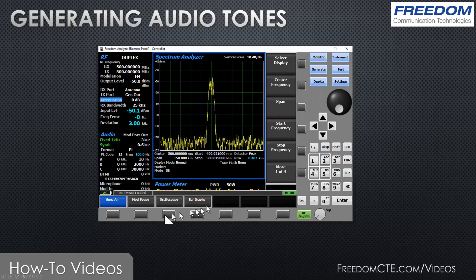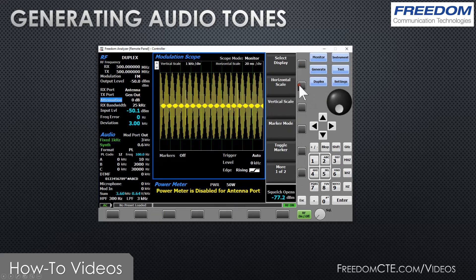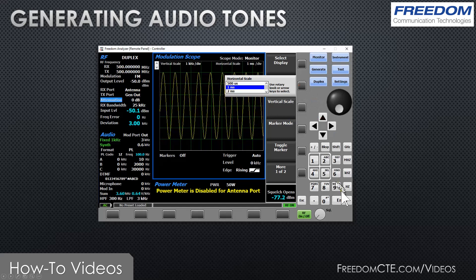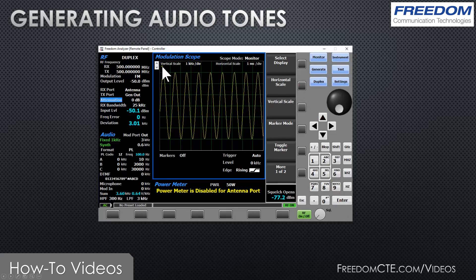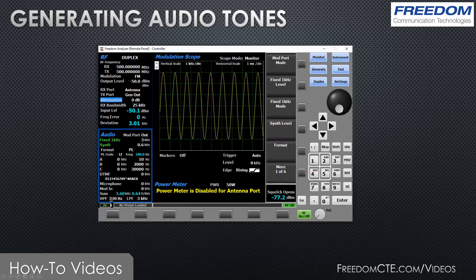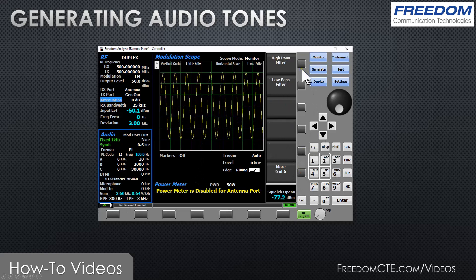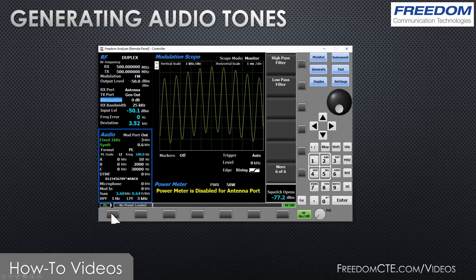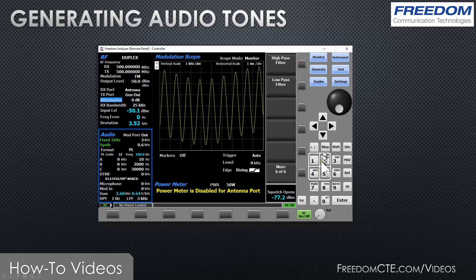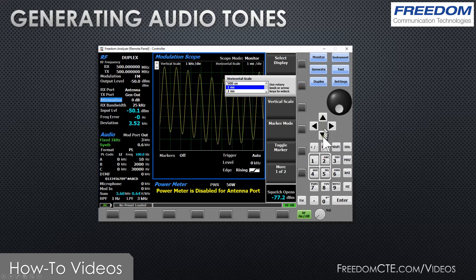I'm going to show you the mod scope. Here we go — I'll change my horizontal scale. Now, for those of you who have noticed already, I'm seeing a one kilohertz tone but I'm not seeing the PL tone, even though it should be there. On the receiving side, you have to remember those bandpass filters. In the audio zone you can see that by default I'm filtering out everything below 300 Hz, so my PL tone has been filtered out. Let's go to the filter and set my high-pass filter to one hertz — and now you can see both the one kilohertz tone and the PL.